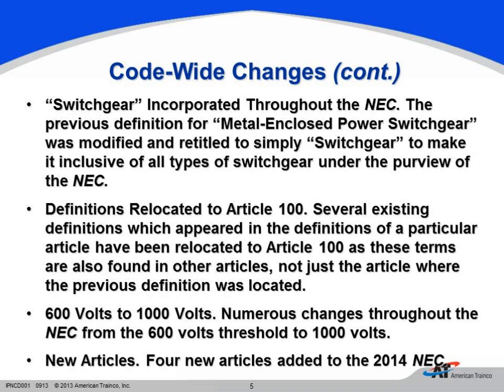New York City subway, 625 volts DC. The MARTA system in Atlanta, Georgia, 750 volts DC. So it was becoming just more and more common, and the task group had a hard time as they went back through the history of the National Electrical Code. They couldn't really determine why the 600 volt threshold was there in the first place. So they felt that it would be very wise to raise that to 1,000 volts so that people could work on that, and we could put some requirements in the National Electrical Code that would help with safety just a little bit.